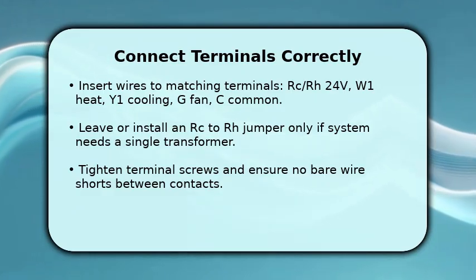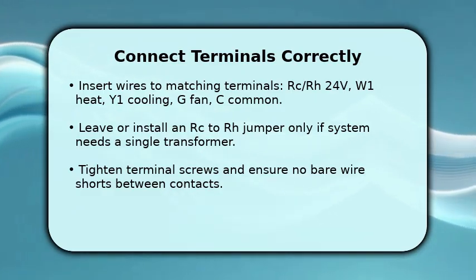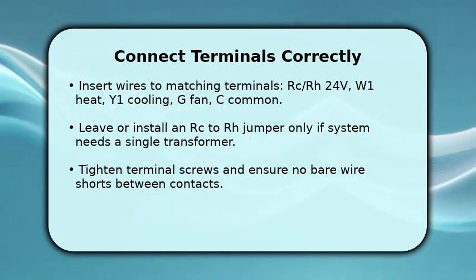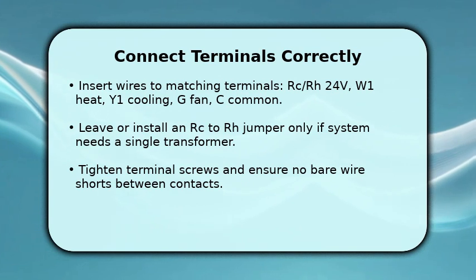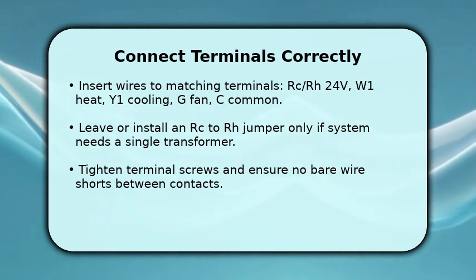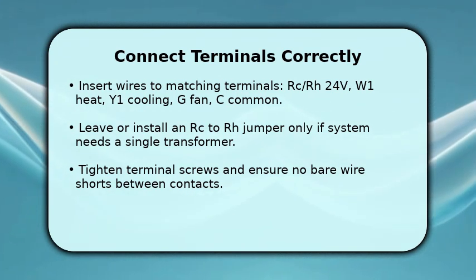Insert W1 for heat stages and Y1 for cooling compressor control. Hook the G wire to the fan terminal and the C wire to common for continuous power. Trim excess wire and ensure no exposed copper contacts can short together.